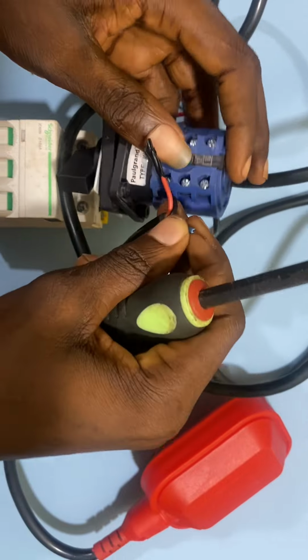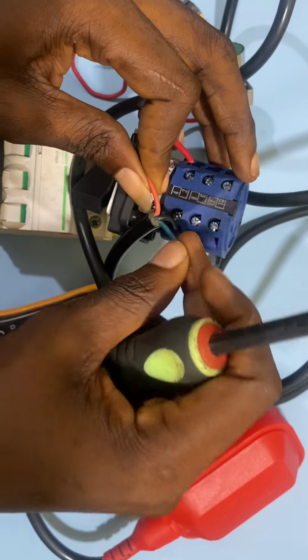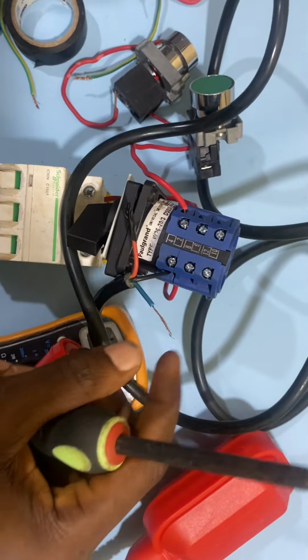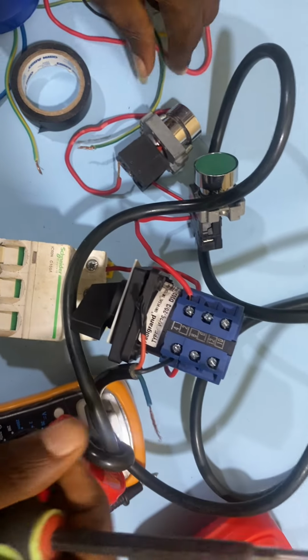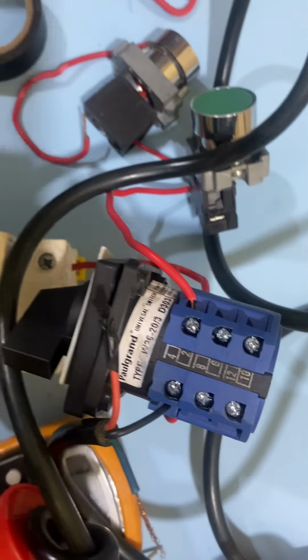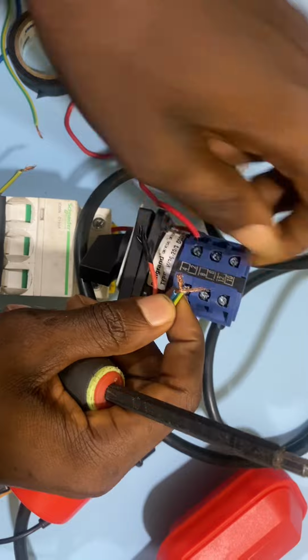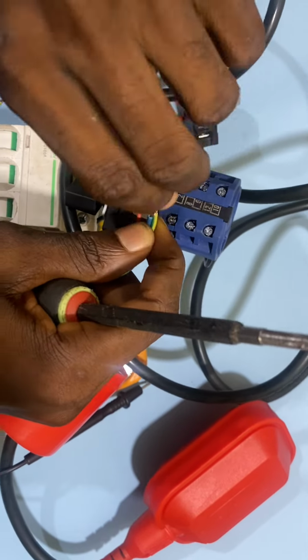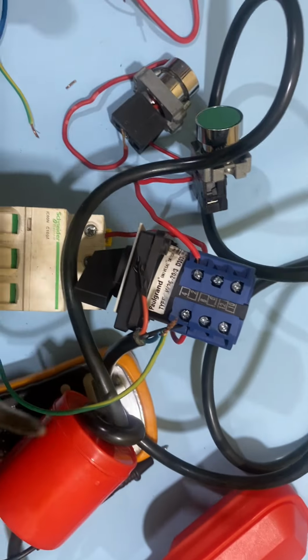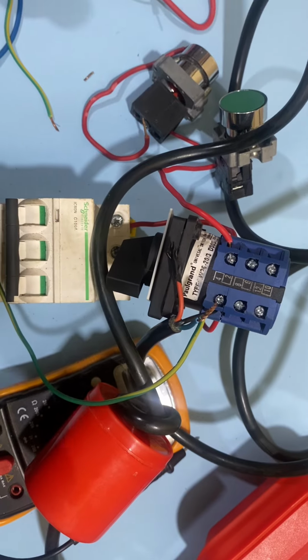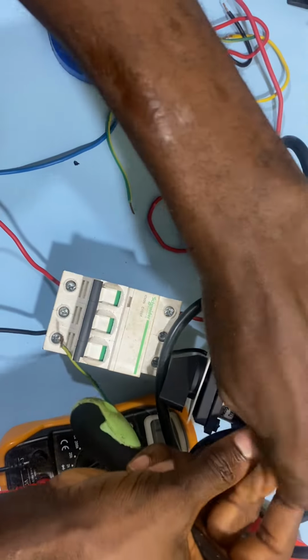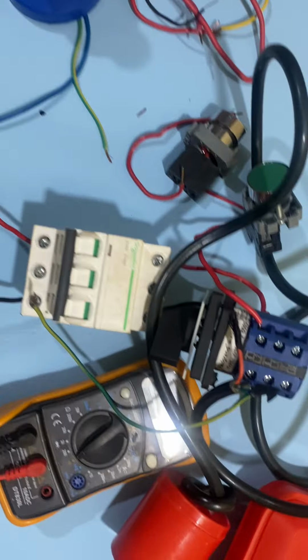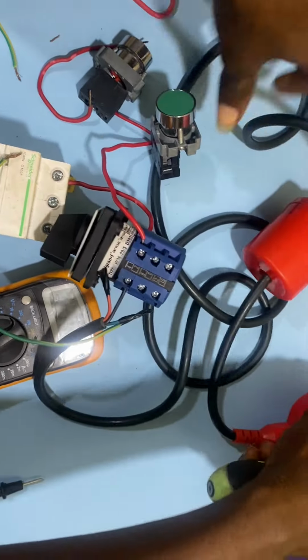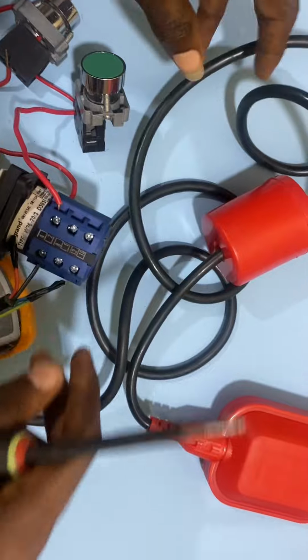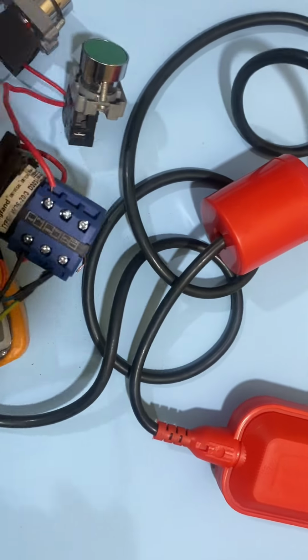Okay, so the next thing now is to connect the common of the float switch, that is the normally open terminal of the float switch, out, so that we'll use it for our load connection. So I'm done with that. I need to insulate it at that point. All right, so I'm done insulating it. So the next thing now is to connect. This is my float switch, pin it that way. So I'm done with the connection of the float switch.